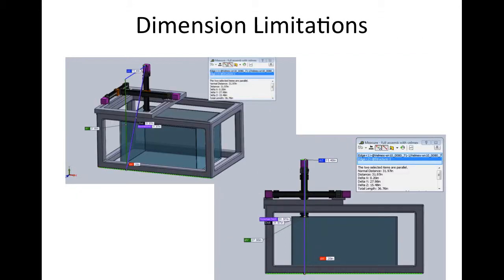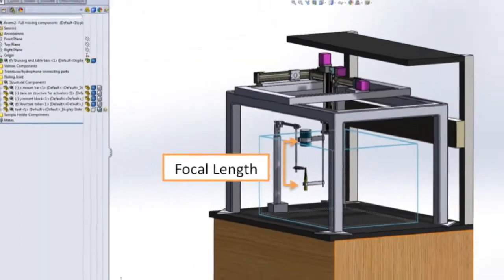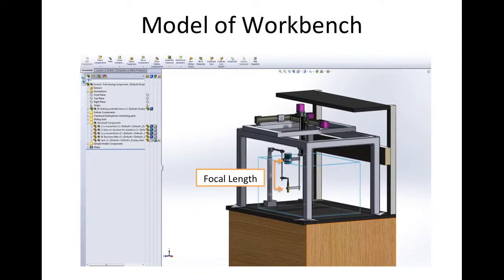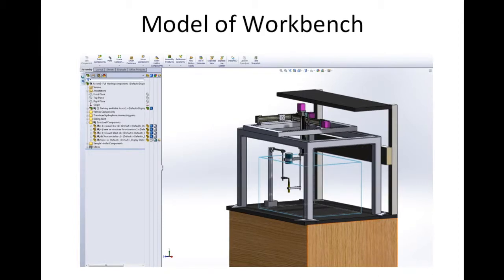Another problem that arose was due to the strict dimension limitations of the workbench and traveling lengths of the vertical actuator. There is a sensitive focal length needed between the transducer and the hydrophone in order to function properly. To help ensure our design fit our workbench and had no interferences with any of the existing features, I made a full model of the workbench. From this, we saw that the vertical actuator would interfere with the top shelf. We could not compromise the length of the vertical actuator or the height that it would be held at.